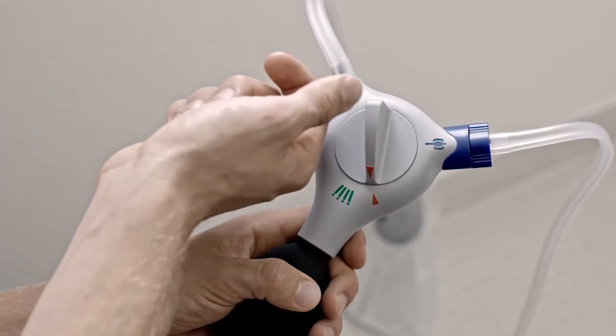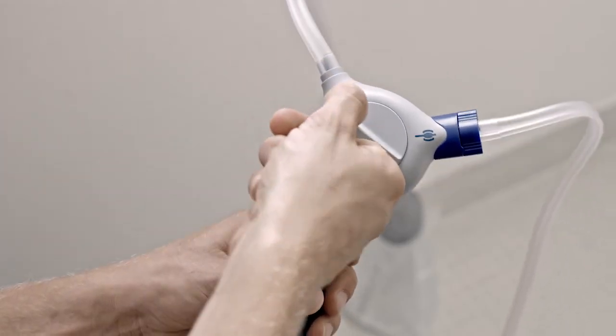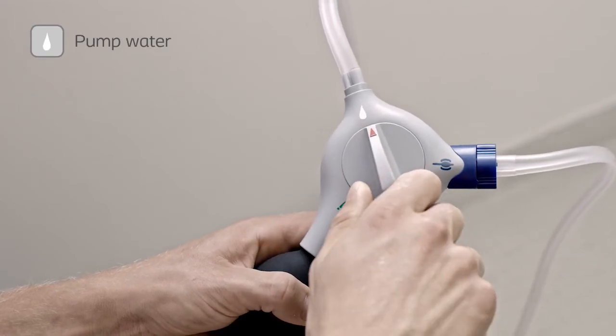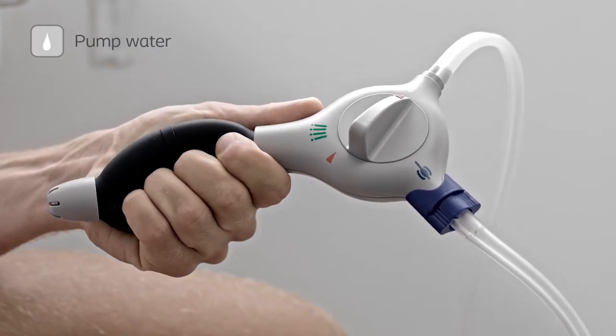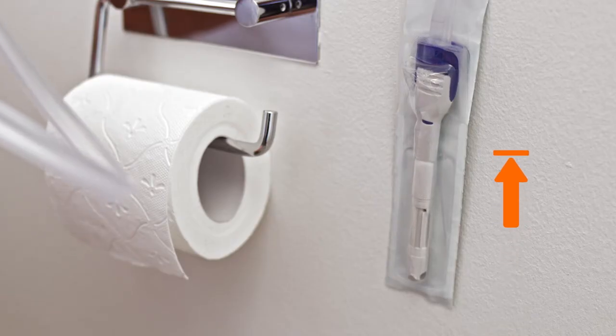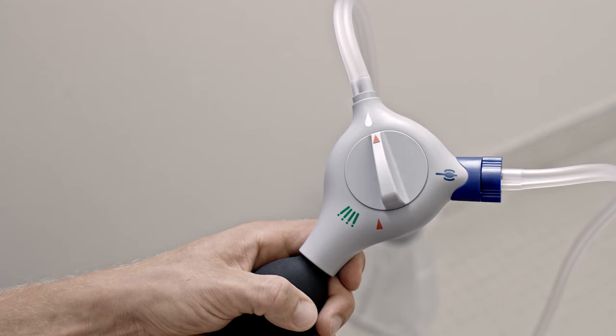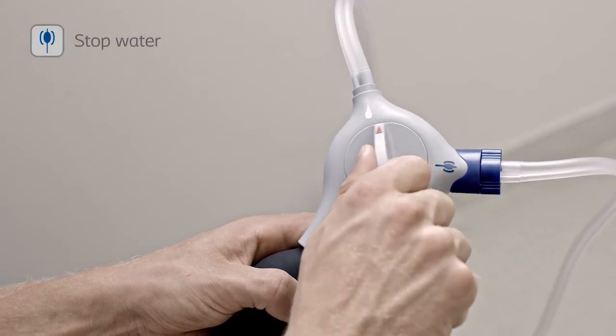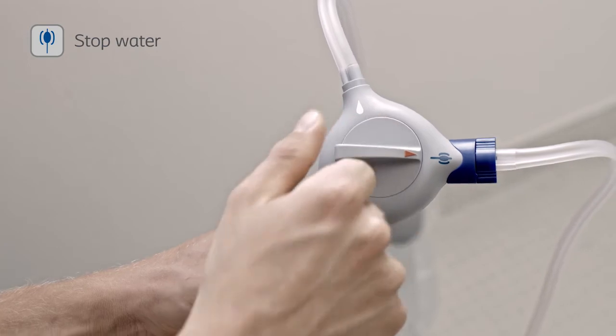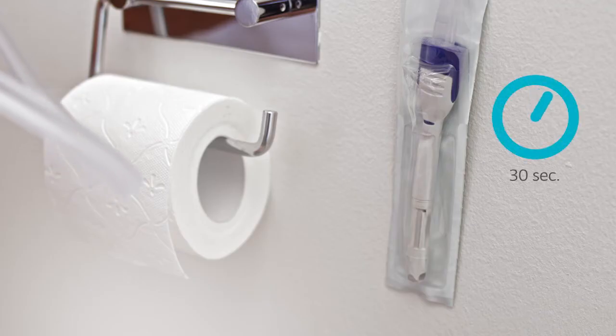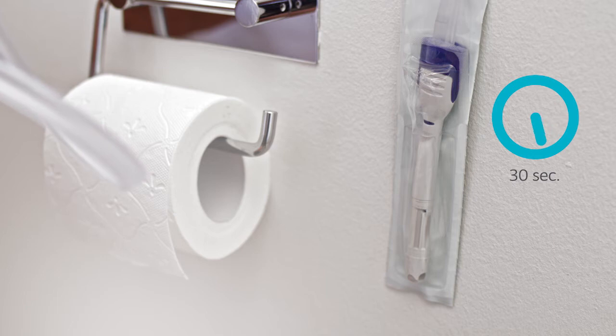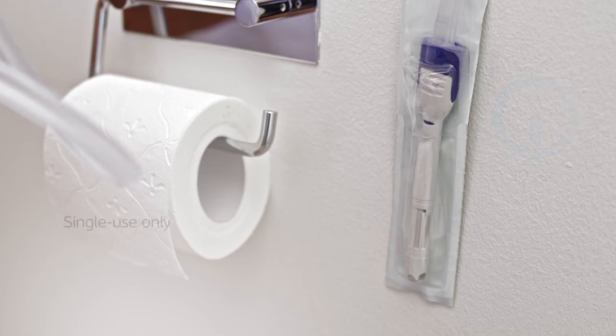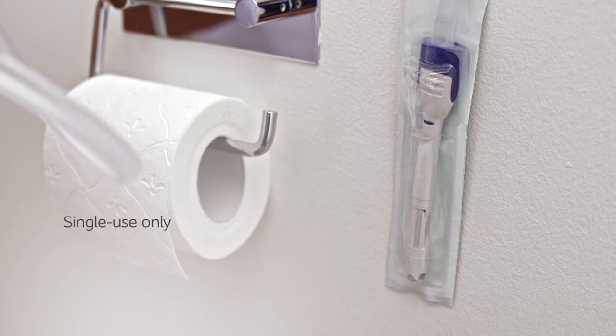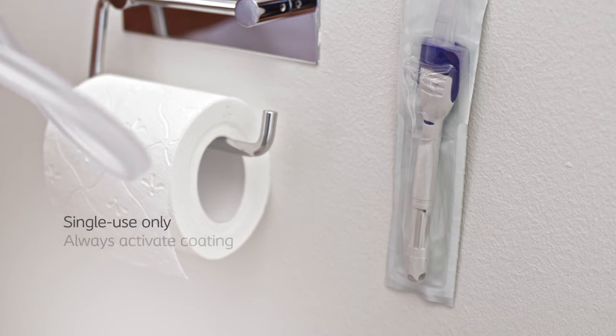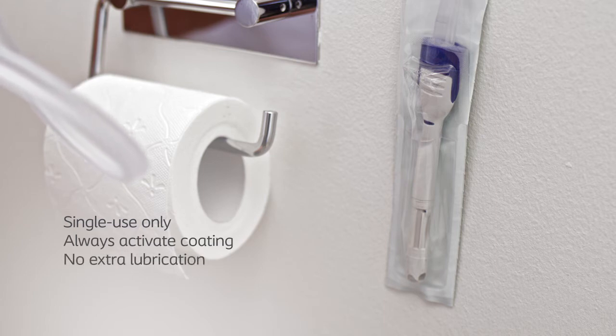To lubricate the balloon catheter, turn the dial on the control unit to the white water symbol. Pump water slowly into the packaging until it reaches the blue line on the balloon catheter. To stop the water flow, turn the dial on the control unit to the blue balloon symbol. Then wait 30 seconds to activate the coating, so it's easy to insert. Remember that the balloon catheter is single-use only. Do not use the balloon catheter without having activated the coating first, and do not use any extra lubrication as it may damage the balloon.